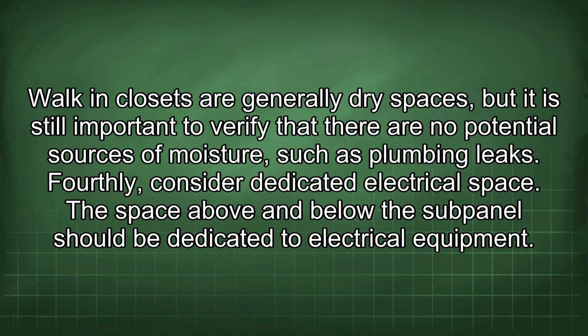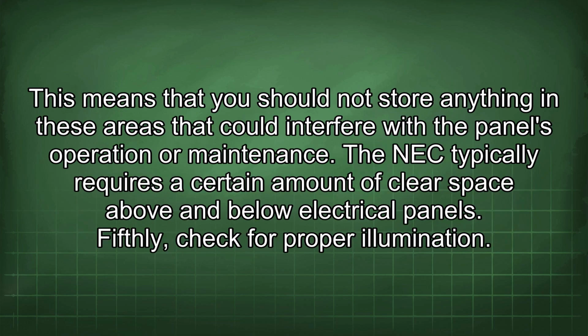Fourthly, consider dedicated electrical space. The space above and below the subpanel should be dedicated to electrical equipment. This means that you should not store anything in these areas that could interfere with the panel's operation or maintenance. The NEC typically requires a certain amount of clear space above and below electrical panels.